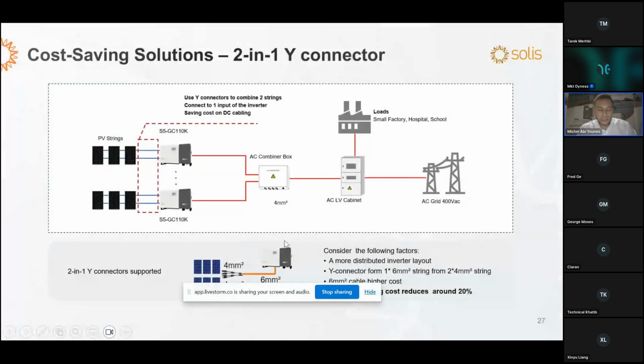Another feature of our inverter is that you can use Y connector on the DC side. So instead of, for each MPPT, we can use a Y connector on the string and go with the cable of one pair of 6 millimeters to the inverter instead of going with two pairs of 4 millimeter, which will reduce 20% of the DC cable cost.